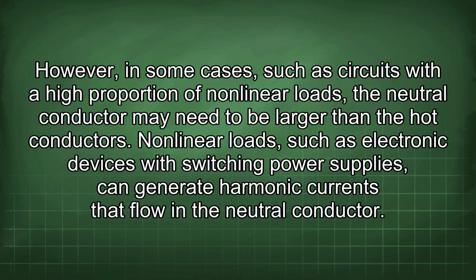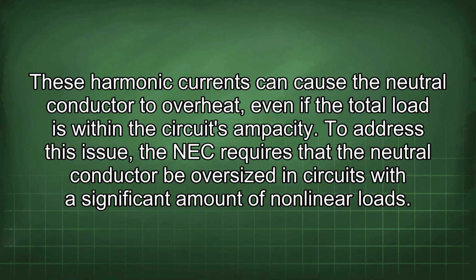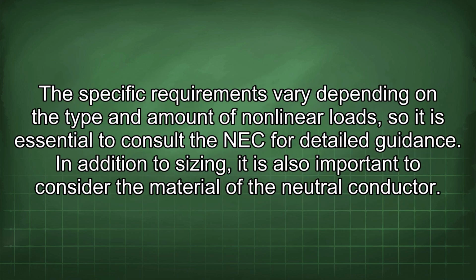Nonlinear loads, such as electronic devices with switching power supplies, can generate harmonic currents that flow in the neutral conductor. These harmonic currents can cause the neutral conductor to overheat, even if the total load is within the circuit's ampacity. To address this issue, the NEC requires that the neutral conductor be oversized in circuits with a significant amount of nonlinear loads. The specific requirements vary depending on the type and amount of nonlinear loads, so it is essential to consult the NEC for detailed guidance.